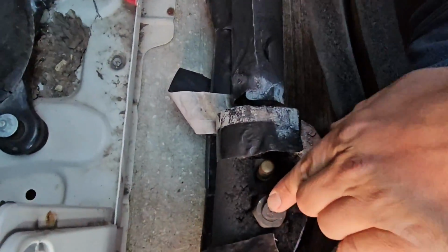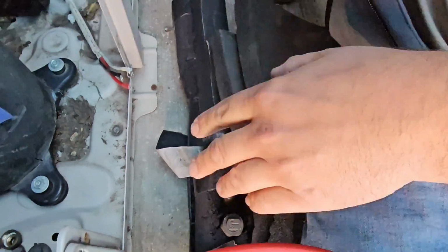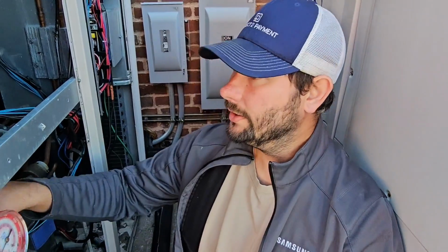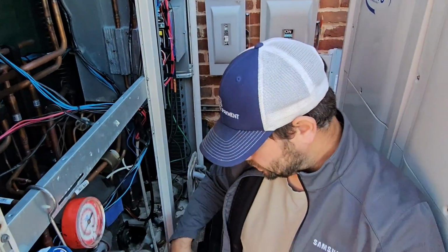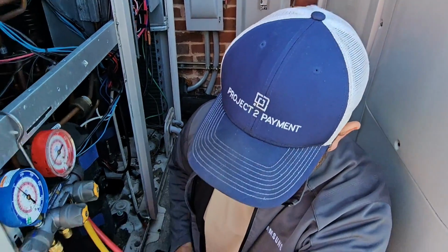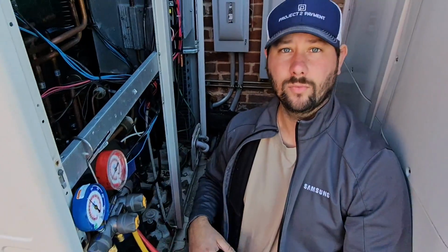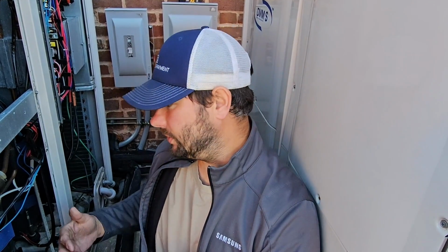See this? These are isolation valves, and I've got them shut off. So we're going to be pulling the refrigerant out of the system from here and from the outdoor unit, from this short set of line sets and then the outdoor unit. So that's the first thing we're going to do, is recover all the refrigerant into our recovery tank, and then we are going to proceed to take out the compressors, and then we're going to get some nitrogen set up, and we are going to braze in the new compressors. Then we'll replace the inverter boards.